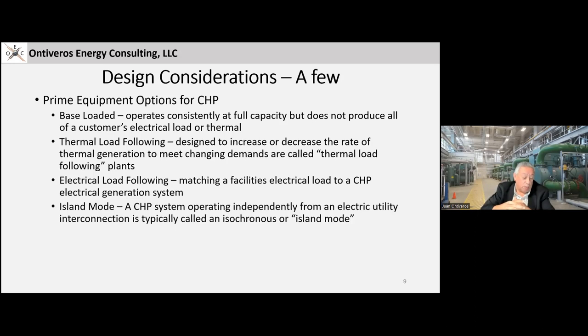You want to be able to think about island mode. Island mode means, in our case at UT Austin, if the grid has problems, we actually do cut off. Most of the time we run in parallel with the grid and use the grid frequency to control our system, but you need to be able to go into isochronous mode or island mode. In our case, we have that feature. That's desirable. For example, I saw in the news yesterday that the Northeast could be going through some blackouts this winter. And so this is something that your client is interested in doing.